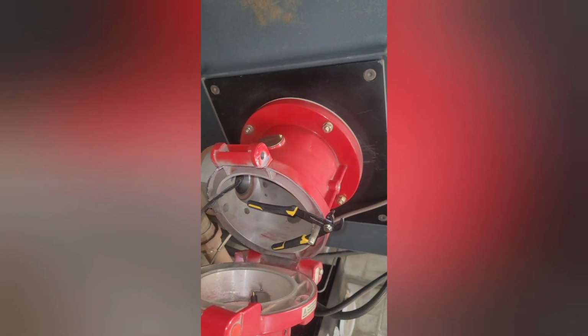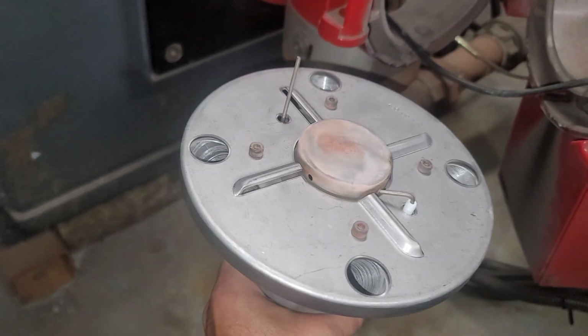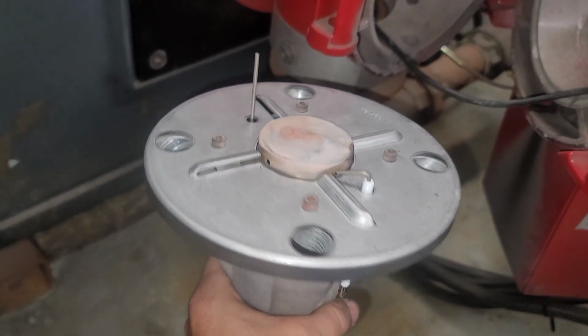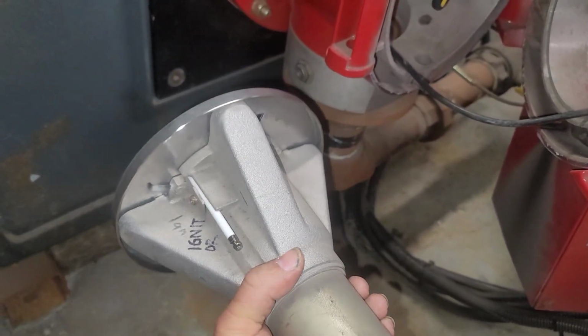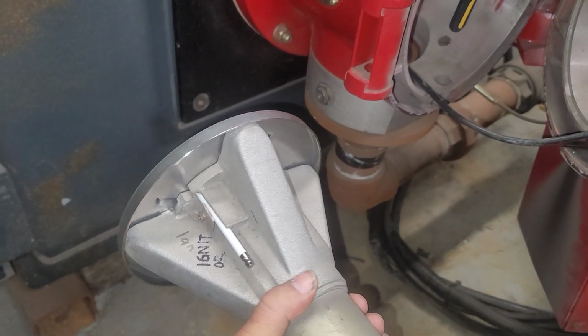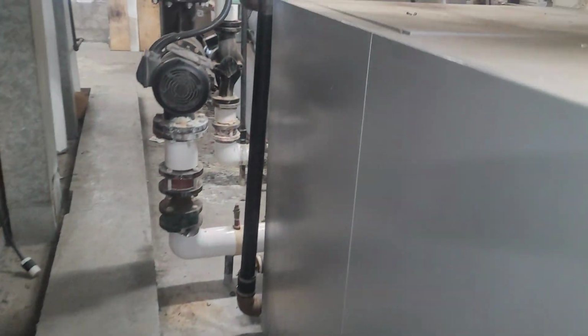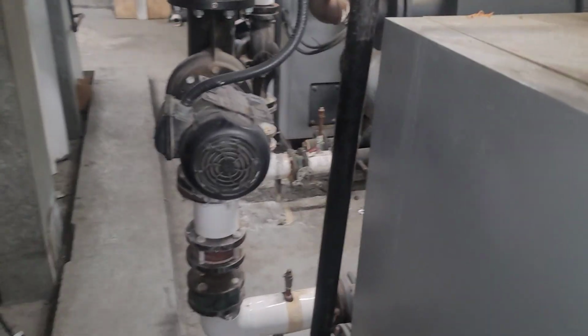So now I'm gonna mount the new burner plate, which I got from the supplier, the same brand, and we have a flame rod and igniter. So let's replace it and test fire. Okay, so I have mounted the plate, new igniter and the sensor. So we're gonna put everything back and test fire it. Okay, so we are ready for test fire.